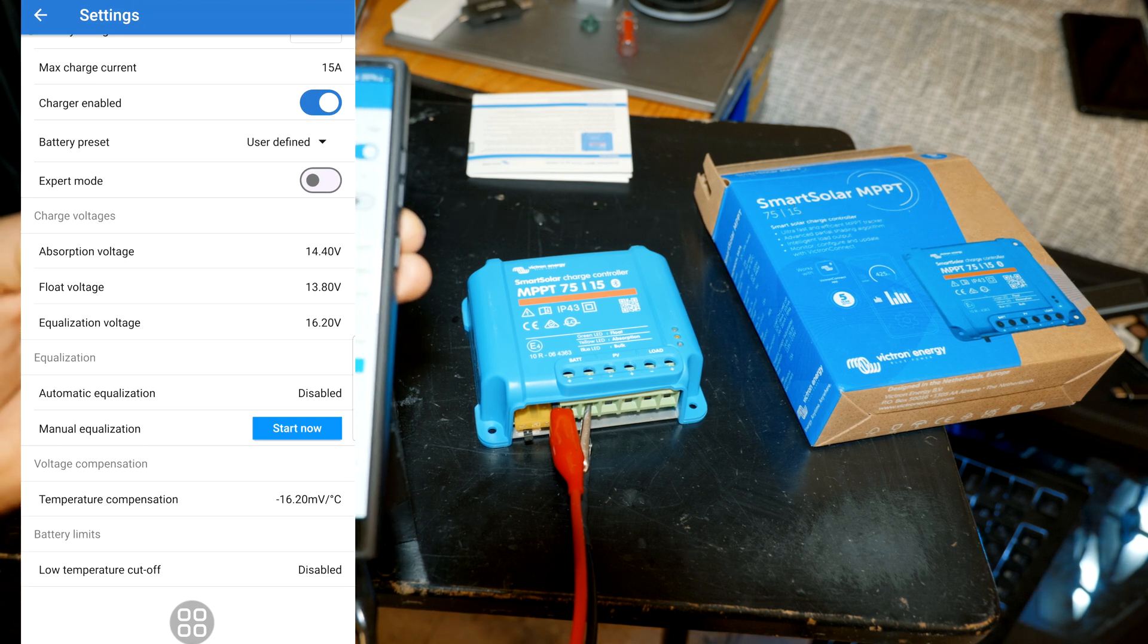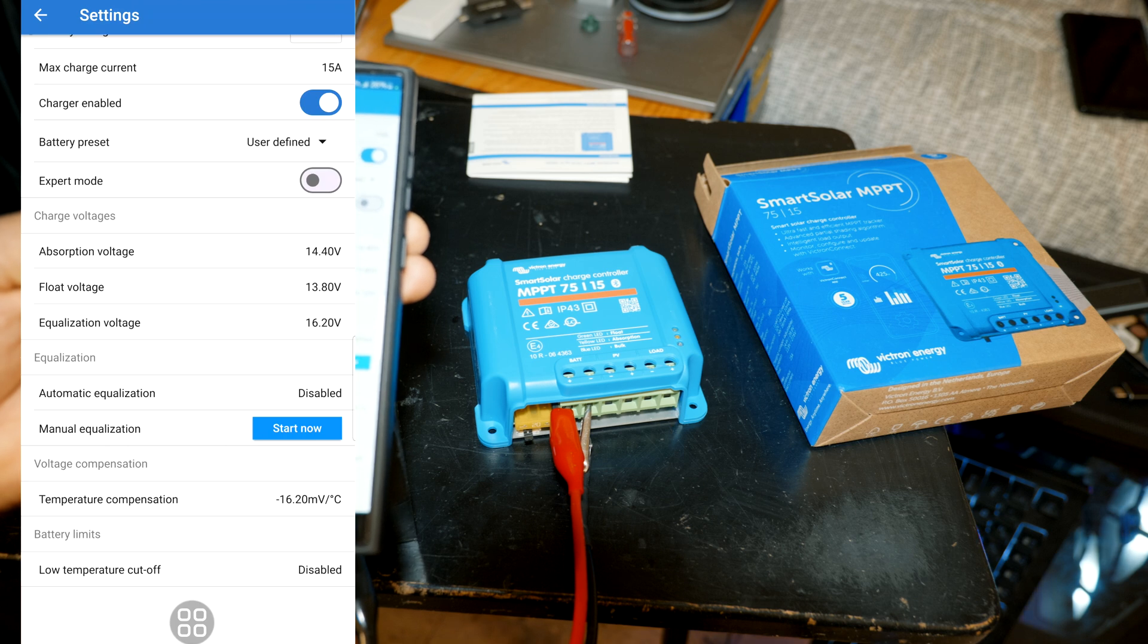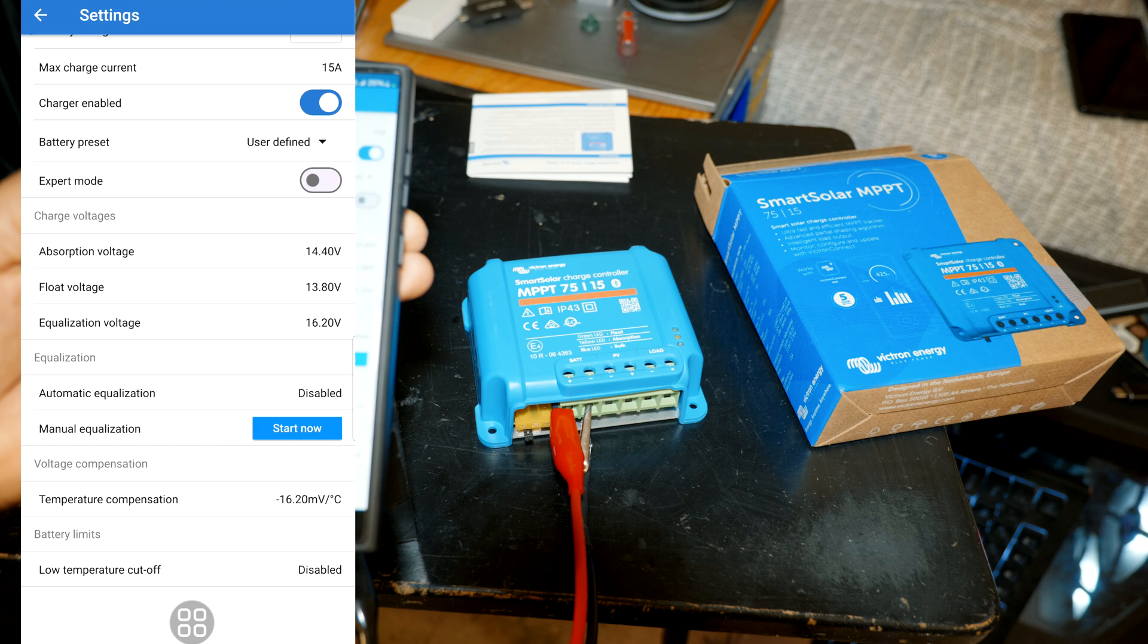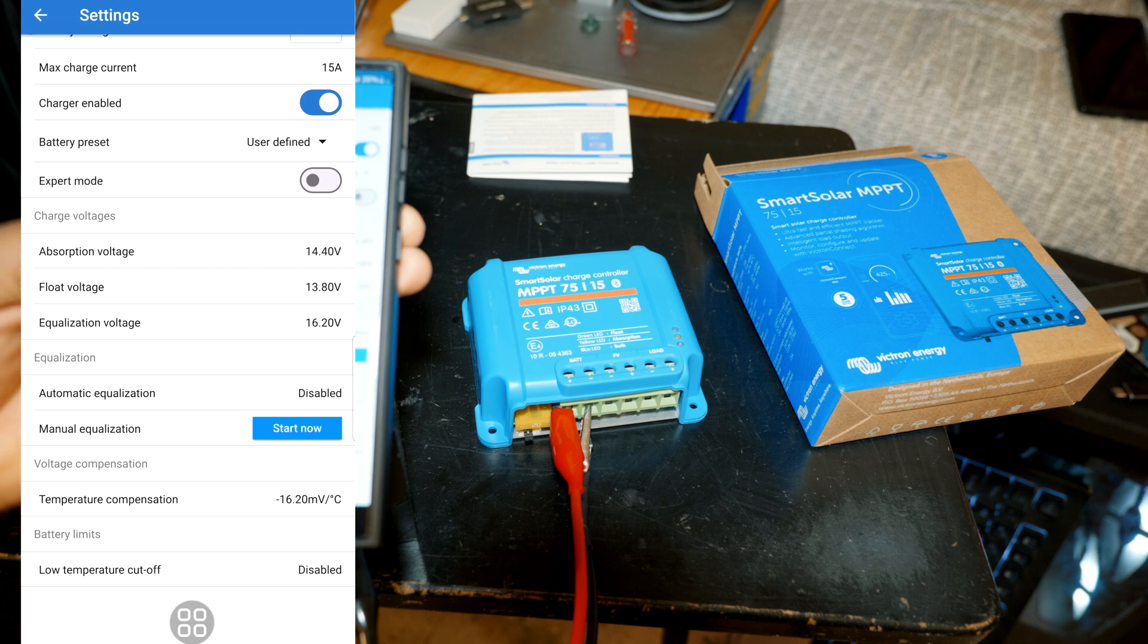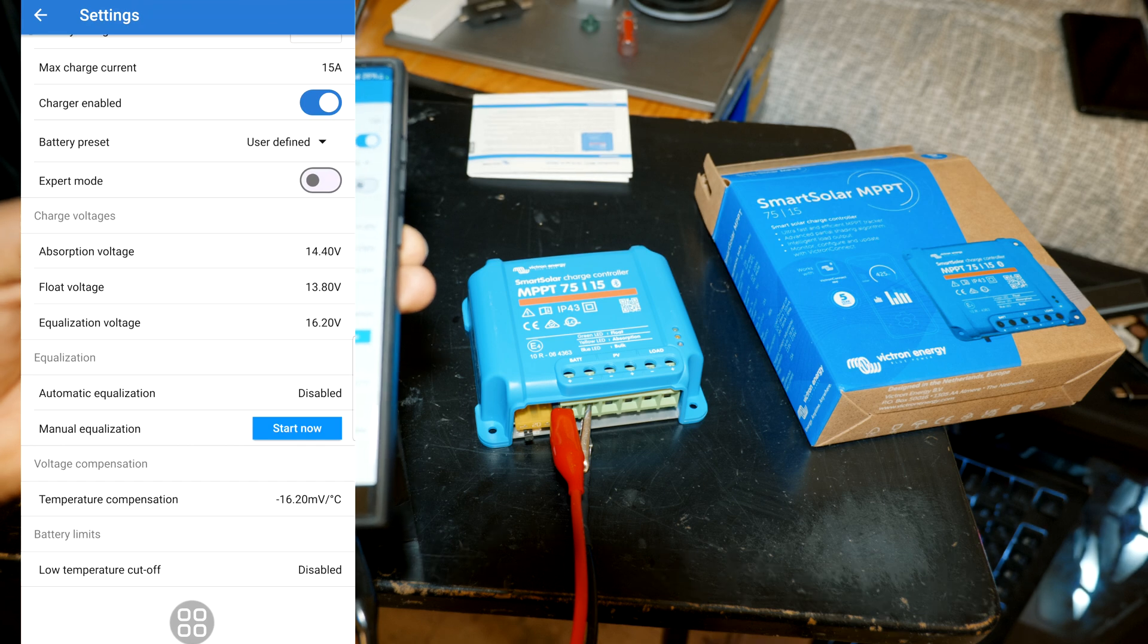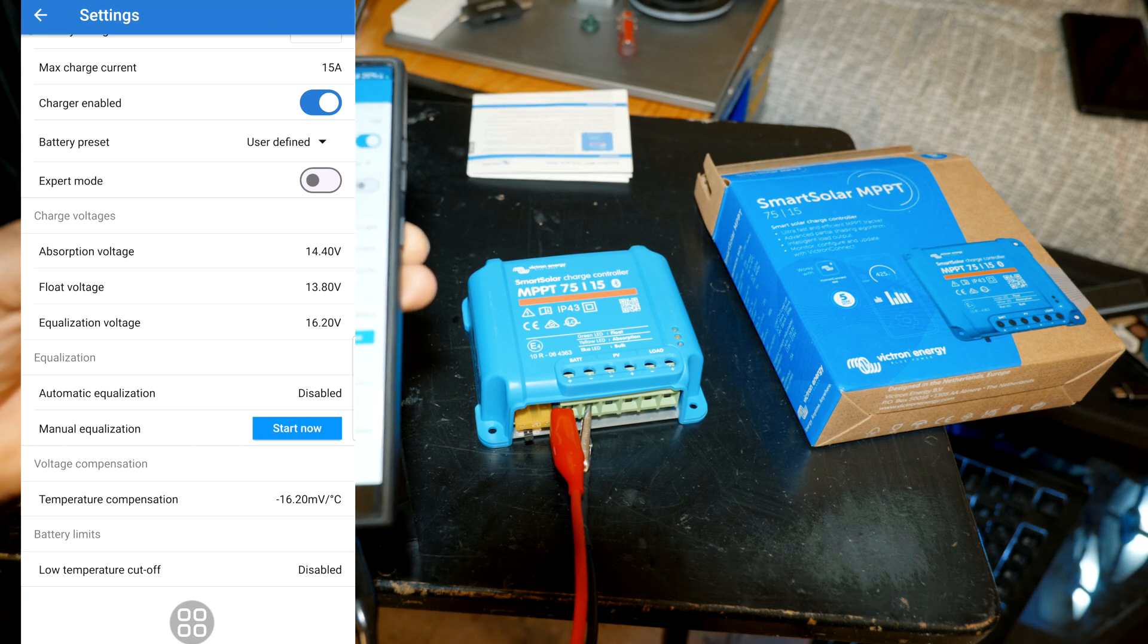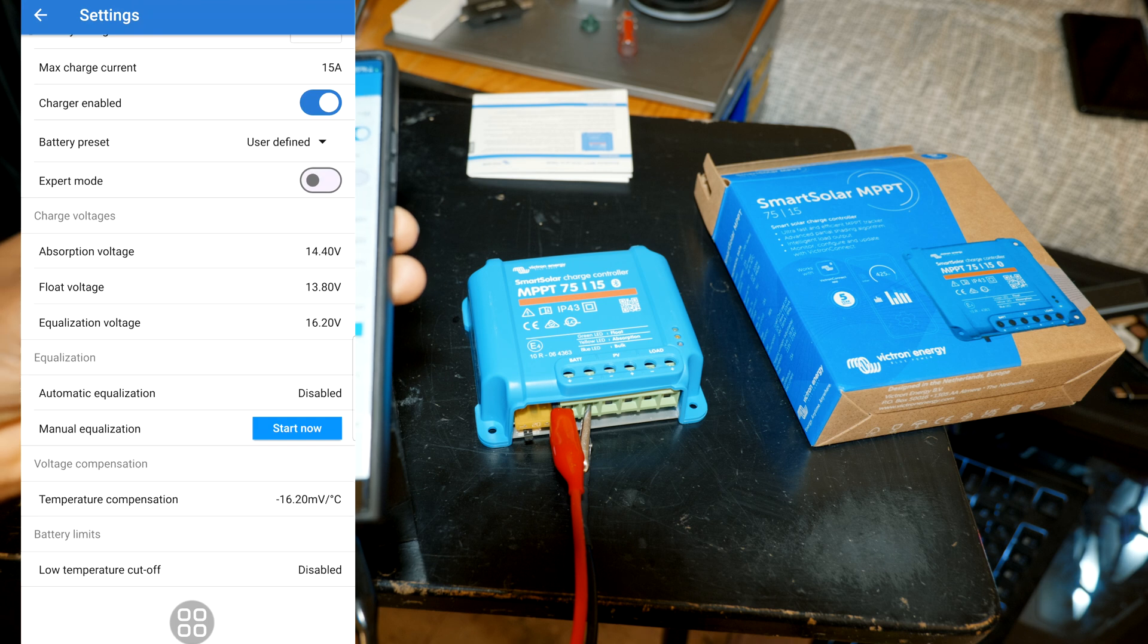Are like throttling options at the end of the charge. When the battery is almost fully charged it's gonna go ahead and trickle and make sure the battery is charged up safely. And then you have automatic equalization which is not required on all batteries, here it's disabled. And then you have a manual equalization function that you can start just by pressing the start now button.